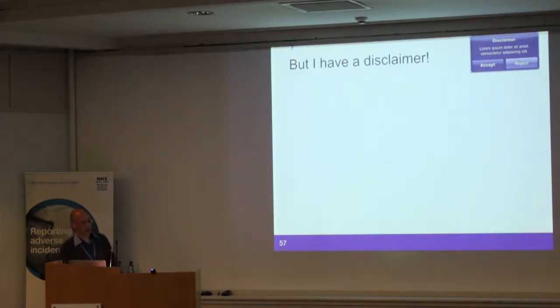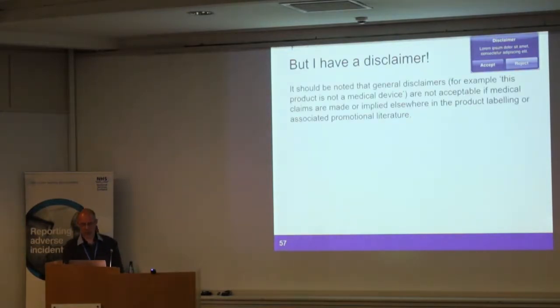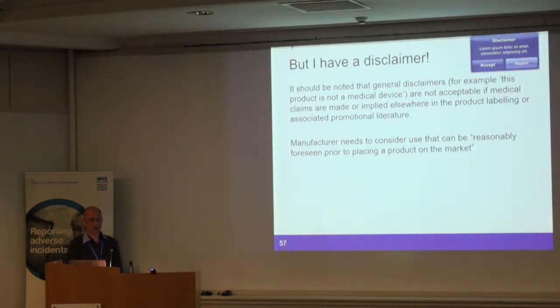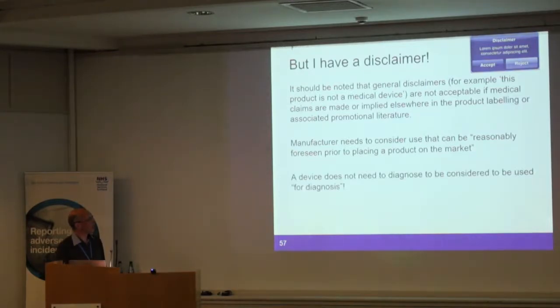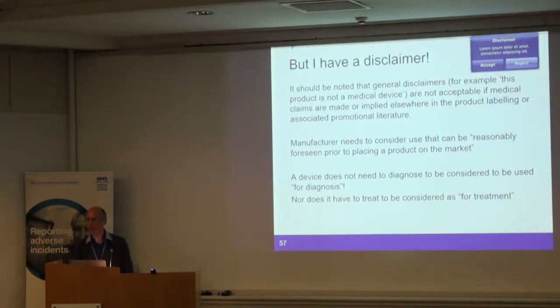Sometimes you see this: "It's not a medical device. I've got a disclaimer." We tend to say that general disclaimers are not acceptable if claims are made or implied elsewhere in the labelling or literature. So manufacturers need to consider what can be reasonably foreseen prior to placing a product onto the market. A device doesn't need to diagnose to be considered to be used for diagnosis, and it doesn't have to treat to be considered for treatment within the definition of a device.